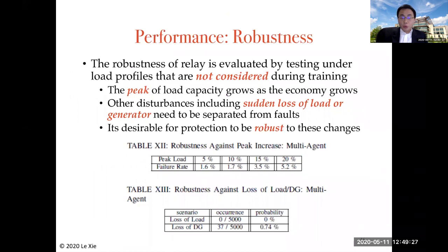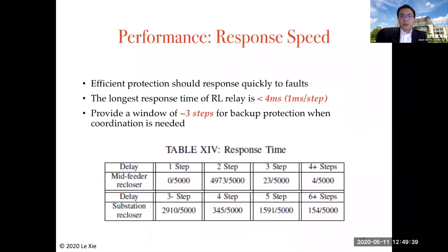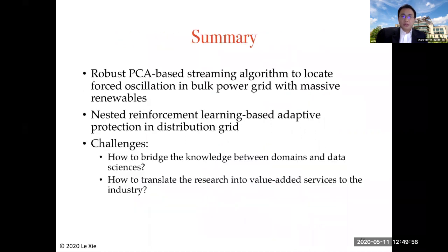And this is also on the robustness: even if you don't know exactly the line parameters and the load profiles, things still work reasonably well under this new paradigm. And this is also the response speed - whenever such a fault happens, you want to clear the fault within a certain time, you don't want to wait too long. It shows very comparable performance with even the traditional relays.